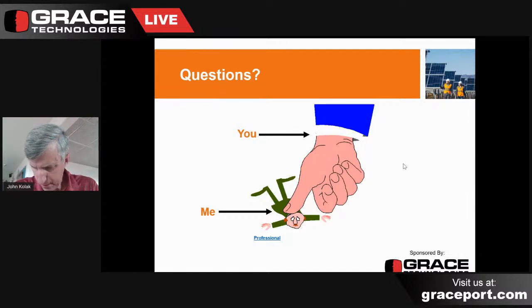The next one is, don't you need to have the switches and circuit breakers in the model to verify the fault duty of the equipment is sufficient? Also, don't they need to be labeled as their equipment that may be interacted with? Yes, you definitely want to put circuit breakers in the system where they exist if they're going to be over duty. Remember, a fuse, we're talking about fault current exposures here. So if you have a switch, the reason we don't worry about that is it's going to stay in the closed position throughout the fault. It's just a solid piece of cable. The reason we're interested in equipment duty is we're expecting that device to interrupt fault current. It's going to act and do something.